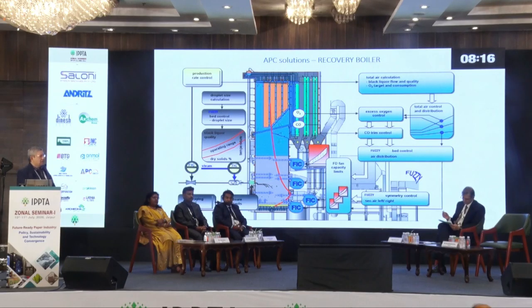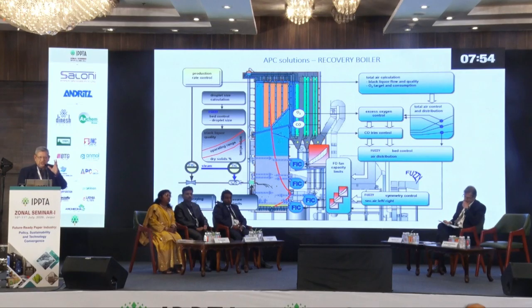This one slide gives you the totality of the recovery boiler control. I hope some of you will be doing it already. You have the combustion control, the liquor control with reference to the feed as well as the temperature, and then how the spraying pattern is, etc. Then how you optimize the whole thing.